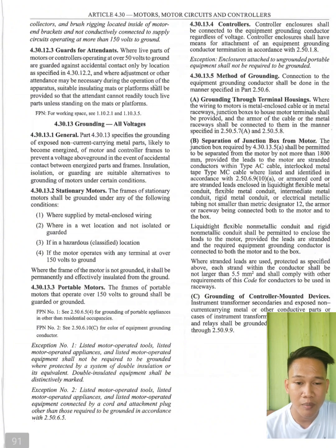4.30.13.2 Stationary motors. The frames of stationary motors shall be grounded under any of the following conditions. First, if supplied by metal-enclosed wiring. Second, if in a wet location and not isolated or guarded. Third, if in a hazardous or classified location. Fourth, if the motor operates with any terminal at over 150 volts to ground. Where the frame of the motor is not grounded, it shall be permanently and effectively insulated from the ground.